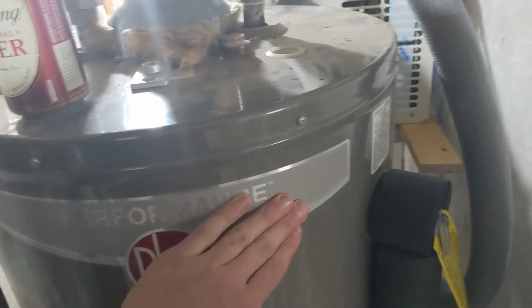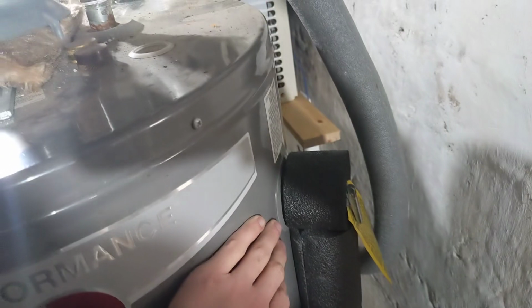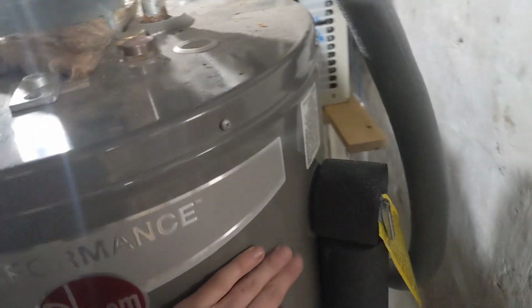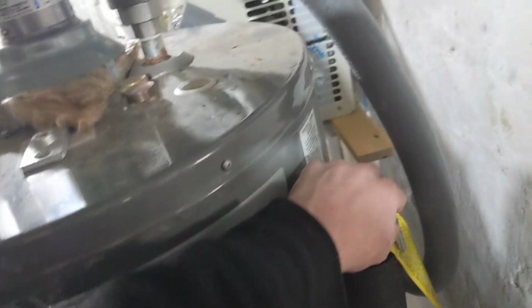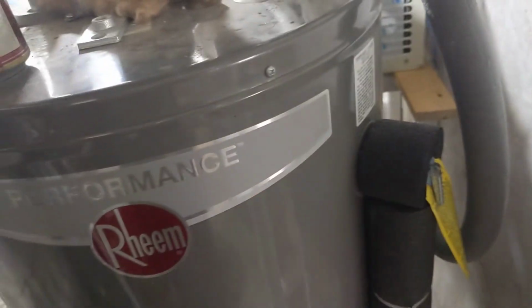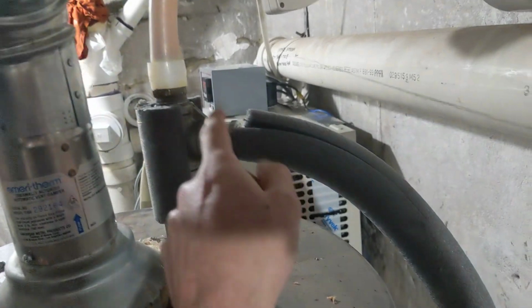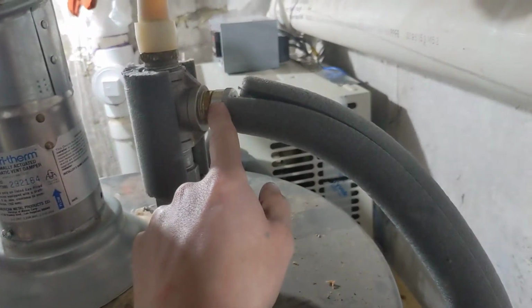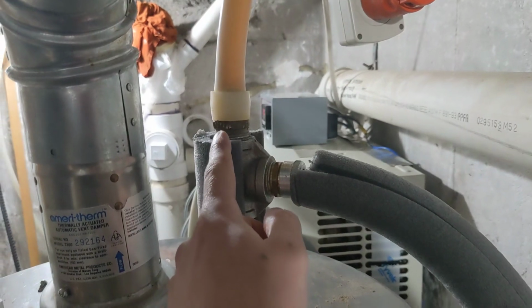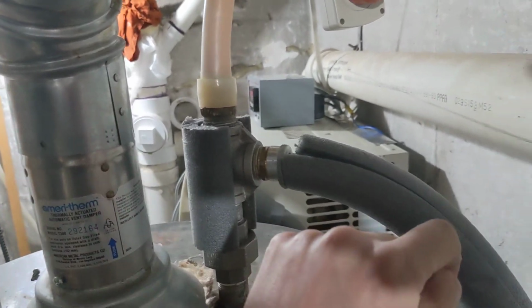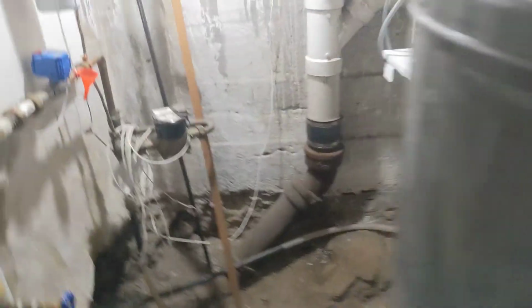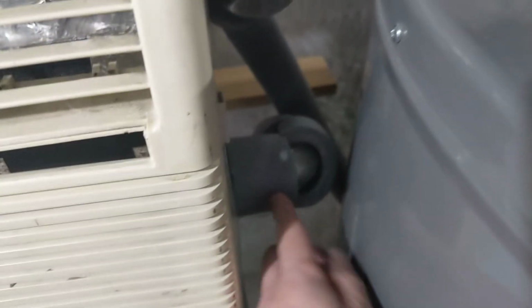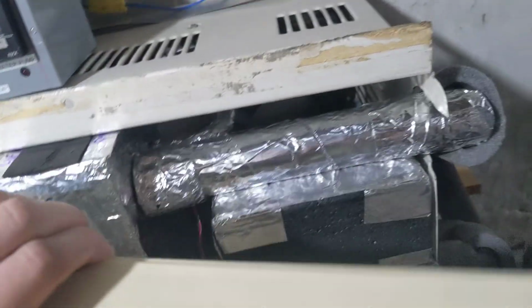Whether it was consuming any extra energy from the heat pump or not, I don't know. But if that was electric or gas, you would never notice it with the energy consumption because the temperature that you're delivering the heat doesn't matter with those fuels. With a heat pump, the colder we can get the water going into the heat pump, the more efficient the heat pump will be. So it's best to take the water right off the cold inlet to the tank. So we're getting the coldest possible water coming in. This is the cold water going in. All right, take the lid off here.